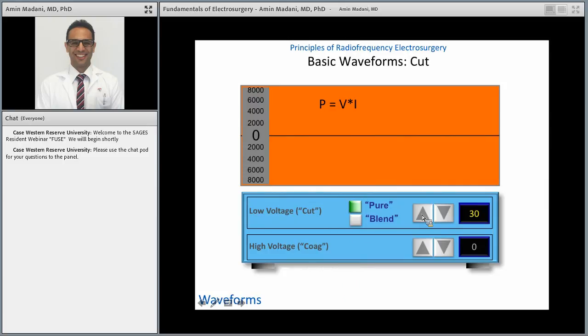This is the current that goes through the circuit. So first of all, it's a sine wave because it's alternating current. So you have alternating positive and negative polarities. But the important thing here is 100% of the time, you have current that goes through the circuit. It doesn't stop at any point. There's always current flowing through the circuit. And because of that, all that 30 joules per second, all that power is spread out through time. That 30 joules per second is delivered, but it's sort of spread thinly. And because of that, the amplitude or the voltage is going to be low. So cut delivers a continuous waveform, but with low voltage.